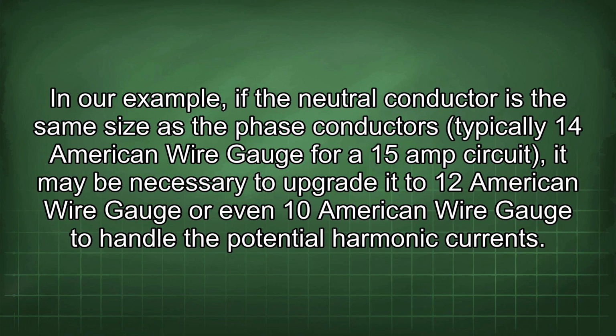In our example, if the neutral conductor is the same size as the phase conductors, typically 14 American wire gauge for a 15 amp circuit, it may be necessary to upgrade it to 12 American wire gauge or even 10 American wire gauge to handle the potential harmonic currents.